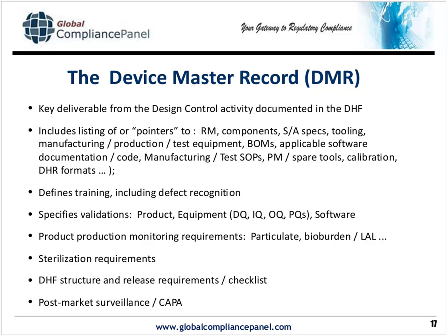The device master record also should require a requirement, as that last bullet point brings out, for CAPA. You should have, if not a specific SOP for this particular product, at least verify that there is an existing SOP for post-market surveillance. Now, true, post-market surveillance by the FDA is generally limited to implantables, but in reality, that general principle applies across the board under your corrective and preventive action system.